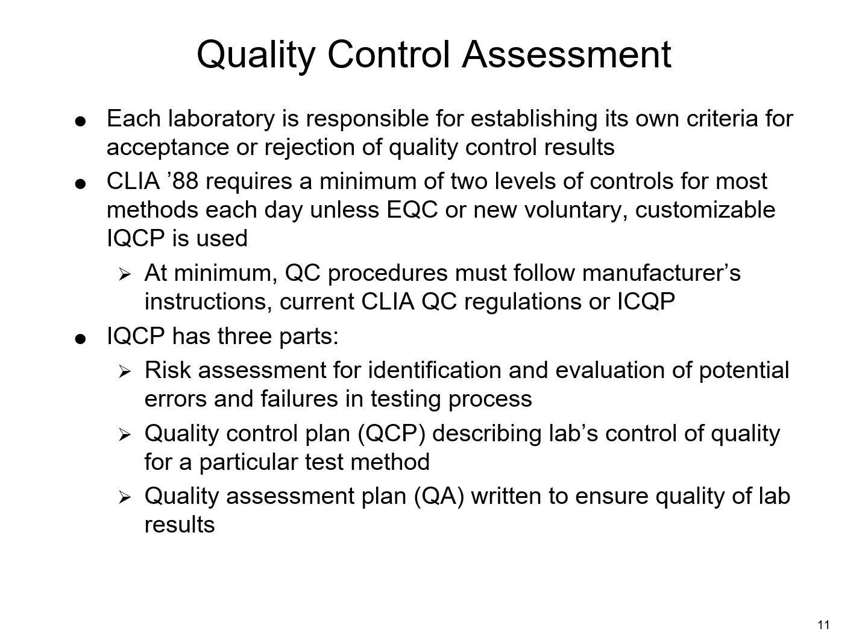Because of the prep process and the steps involved with the actual testing of that sample, it is considered a high complexity test. Now granted, your cartridges have built-in quality control in them, and it has different checks and balances that it does each time you run a test on that iStat machine.